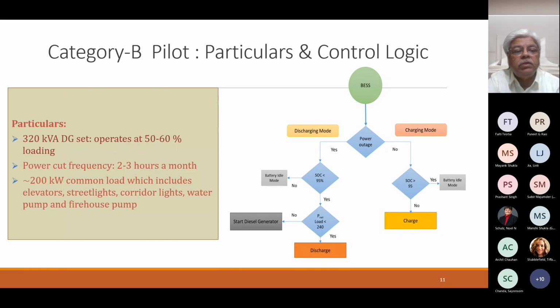Since our common load was about 200 kilowatt, to be on the safer side, a limit of 240 kilowatt was set. If the load is less than 240 kilowatt, we discharge through the battery. If the load is more than 240 kilowatt, we start the diesel generator set.